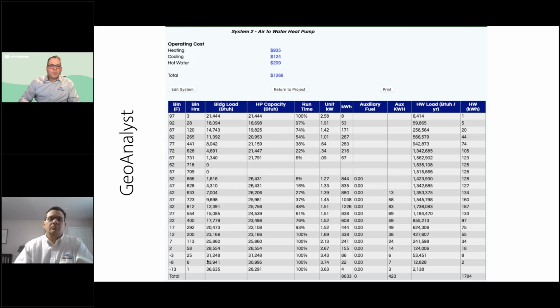Bin data is what's really most important. This is Syracuse right here. You can see all the way down to -13. We only have 1 hour per year on a 20-year typical weather average here. And if you look at the bulk of the bin hours in that 12 degree to 47 degree range, that's really where our operating is.